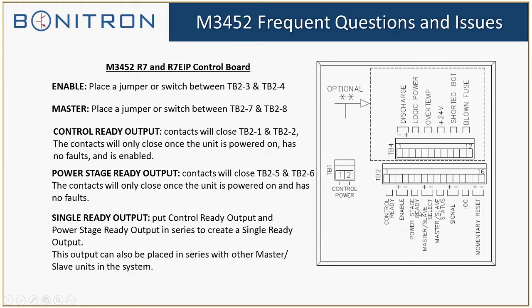The only thing that customers need to realize is that there's a small voltage drop across each of these contacts. So if your PLC is not configured correctly, it could show up as being open all the time when it's not, and the contacts are actually closed. So that's been a very rare occurrence. I believe it's only happened 2 or 3 times that I can recall when customers were trying to set it up. But once they realize that, they can just retool their PLC or pump in a slightly higher voltage going across these contacts, and that solves the issue.